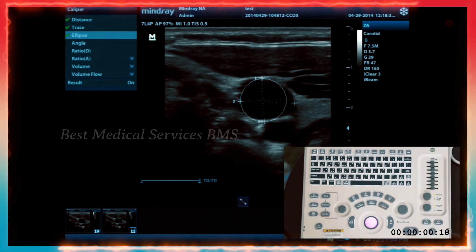In this chapter, we're going to discuss annotations and some other features aside from just imaging. We have a body marker button, an ABC comments button, and an arrow button just to the left of the space bar. If you want to start typing on the screen, go ahead and hit freeze and then just start free typing. You'll see that the ABC comment key is automatically engaged, putting you in annotation mode. The menu now shows a bank of words for the exam preset you're in — here we're in OB second/third trimester setting, with a nice bank of commonly used annotation words.